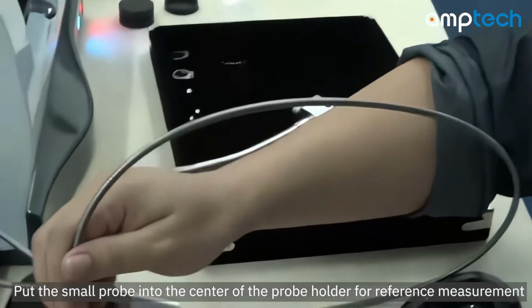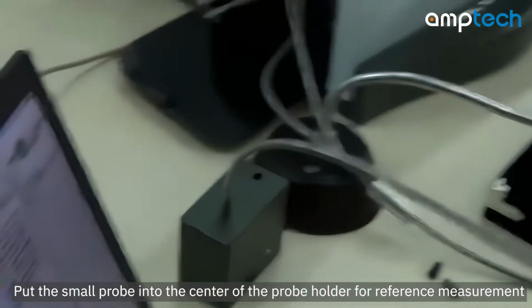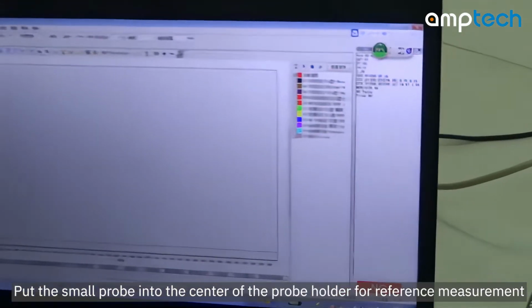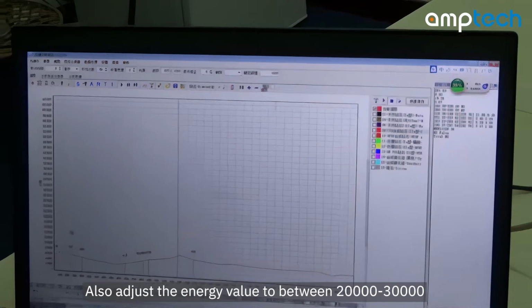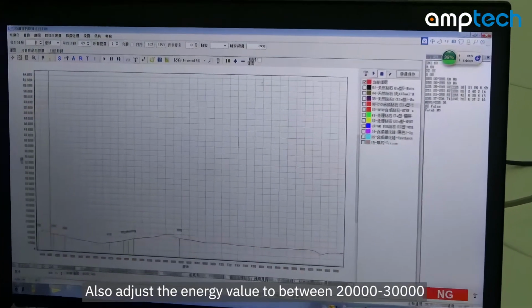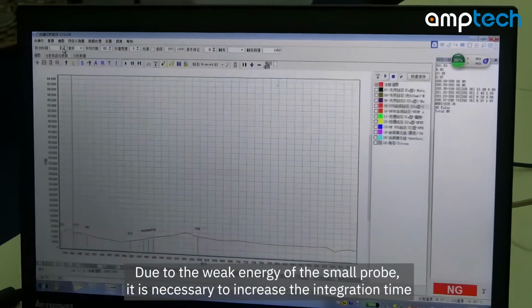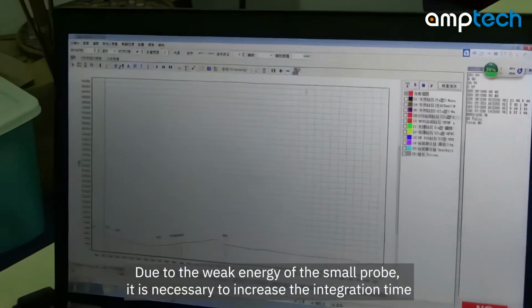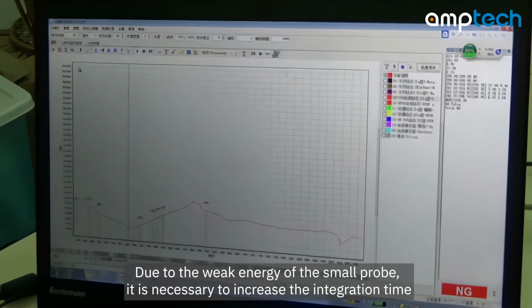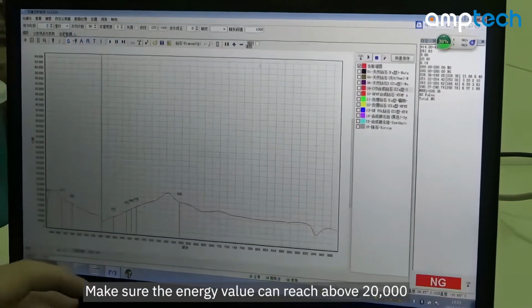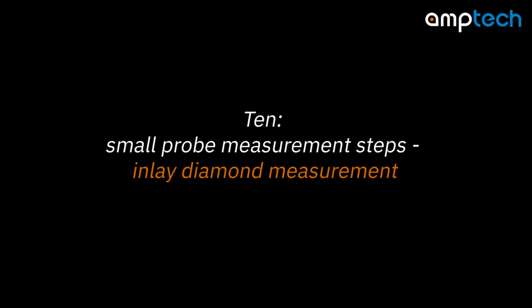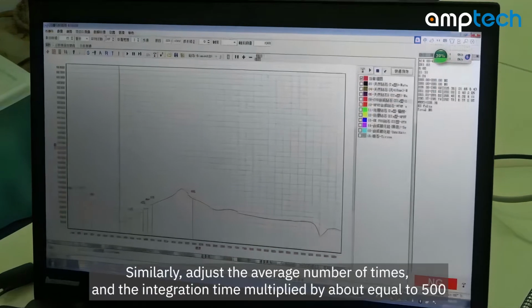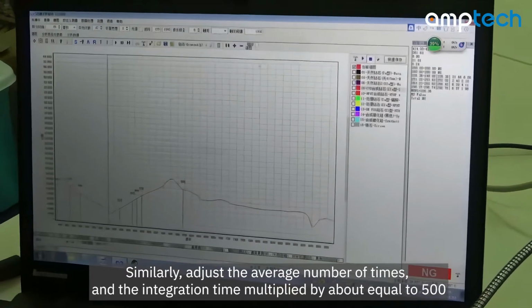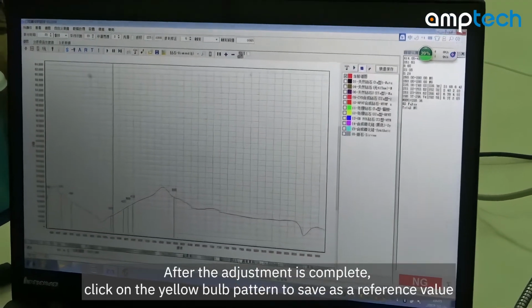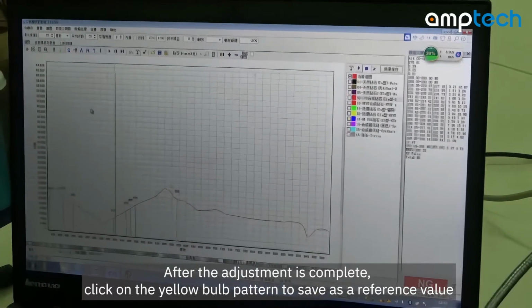Put the small probe into the center of the probe holder for reference measurement. Also adjust the energy value to between 20,000 to 30,000. Due to the weak energy of the small probe, it is necessary to increase the integration time. Make sure the energy value can reach above 20,000. Similarly, adjust the average number of times, and the integration time multiplied by it should be about equal to 500. After the adjustment is complete, click on the yellow bulb pattern to save as a reference value.